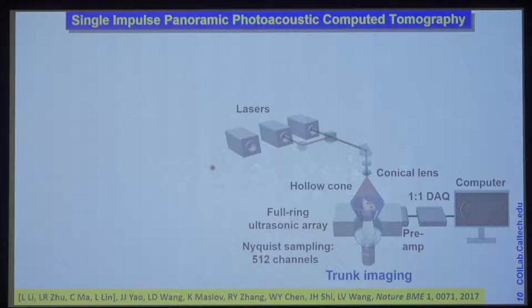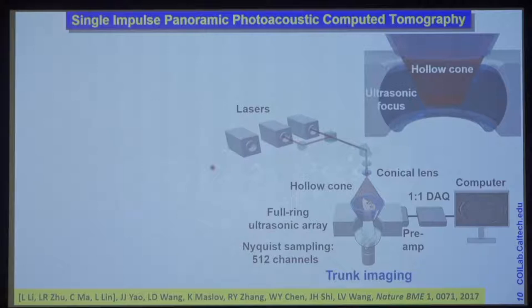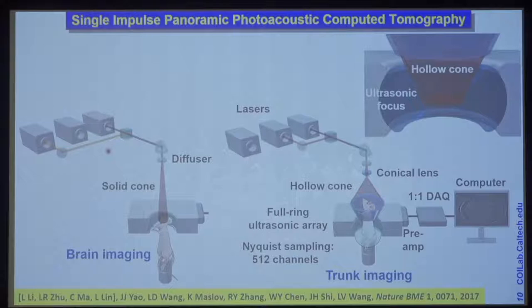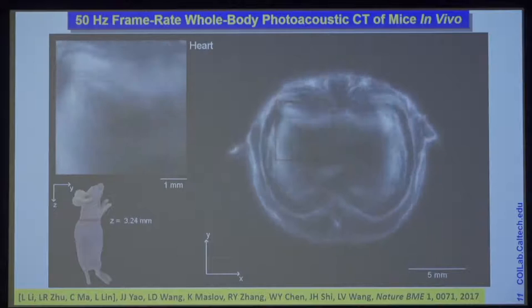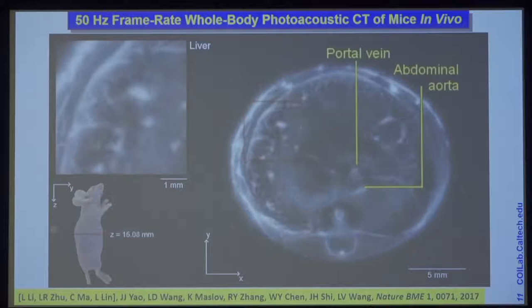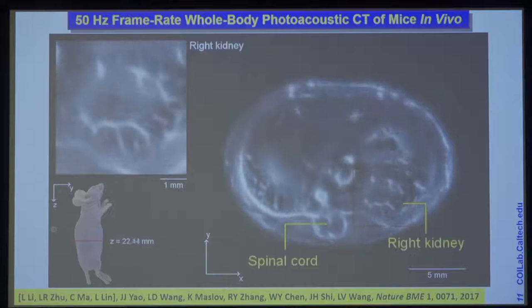Here's a close-up. We have a hollow cone beam for focusing, ultrasonic focusing for elevational resolution, and lateral resolution comes from the inverse spherical Radon transformation. The system can also be used for brain imaging using a diffuser to generate a solid cone beam instead of a hollow one; the rest of the system is very much the same as trunk imaging. We fire the laser at 50 Hz pulse-repetition rate, giving a 50 Hz frame rate, though you can fire up to even kilohertz — so this is an extremely fast technology.